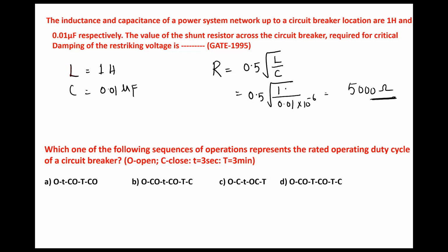So immediately for the first tripping, the operator will simply go, reset and close the circuit breaker. He will not check why it has happened, what is the reason, no. Because 80 to 90% of the faults are transient faults. He will assume that if he presses the reset button and the system becomes normal, he will not do any other thing.